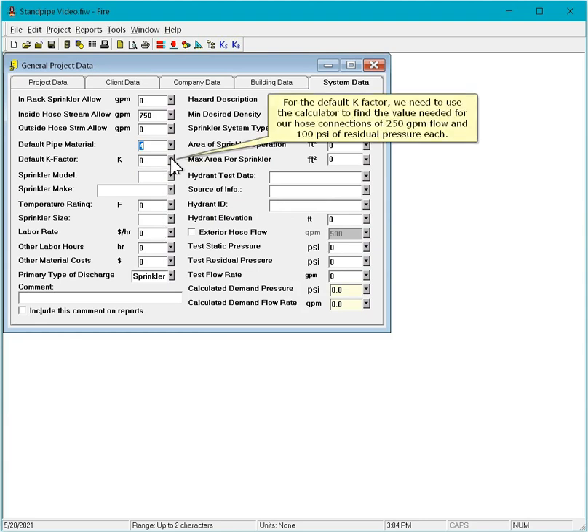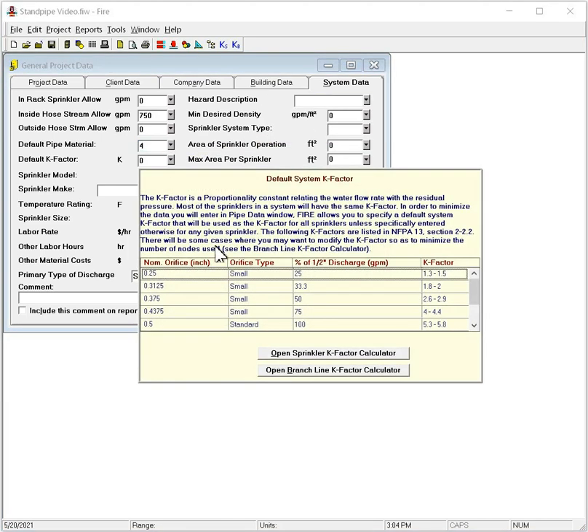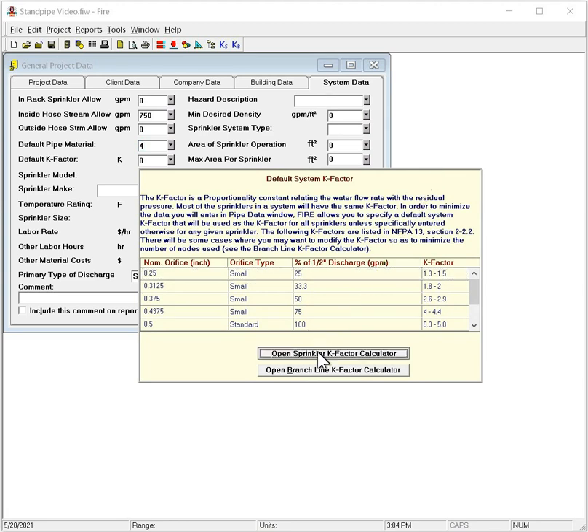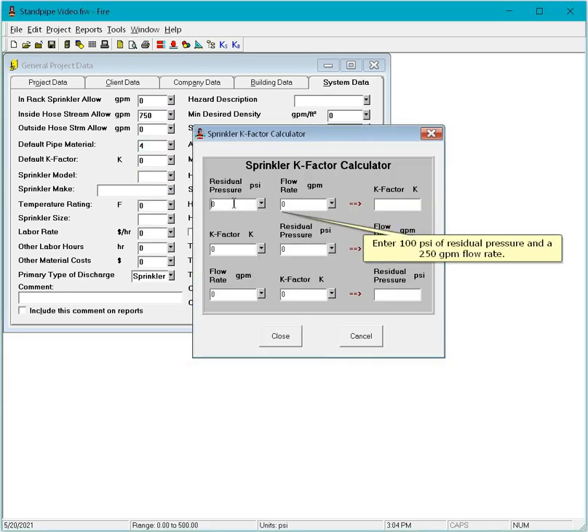For the default k-factor, we need to use the calculator to find the value needed for our hose connections of 250 GPM flow and 100 PSI of residual pressure each. Click the Open Sprinkler k-factor calculator button. Enter 100 PSI of residual pressure and a 250 GPM flow rate.